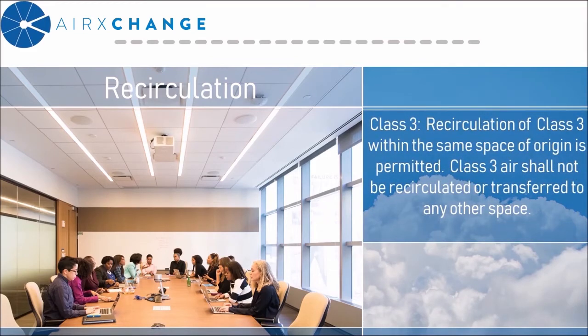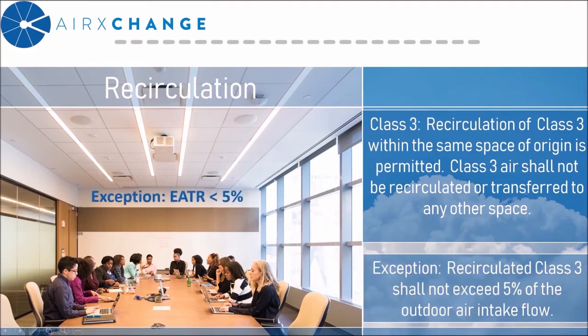For Class 3, recirculation within the space of origin is permitted, and Class 3 air shall not be transferred to any other space. However, there is an exception when using an energy recovery device: recirculated Class 3 air shall not exceed 5% of the outdoor air intake flow, which means your EATR must be limited to 5% or below.